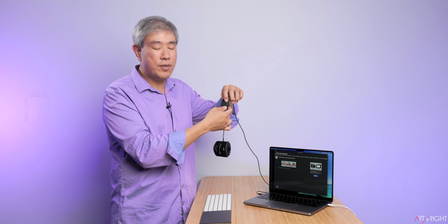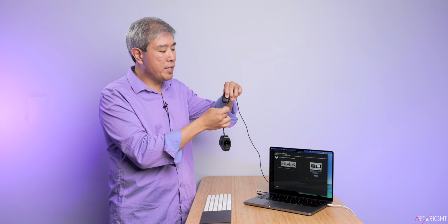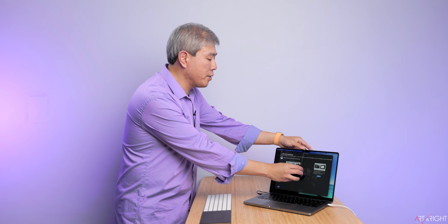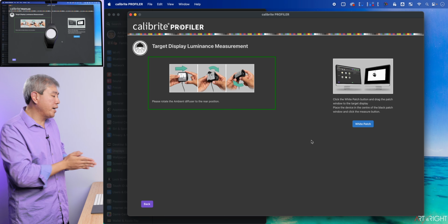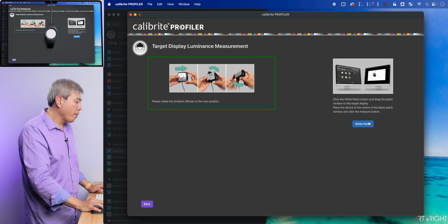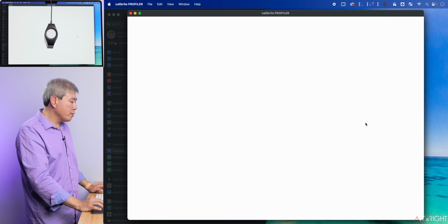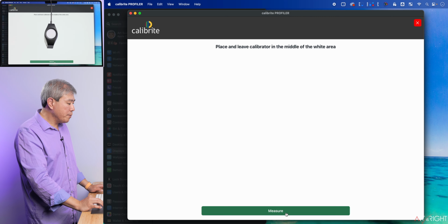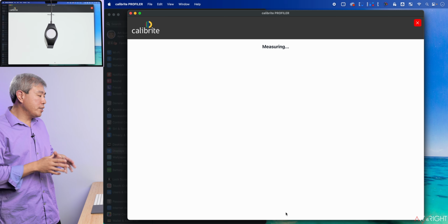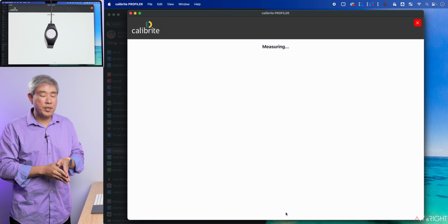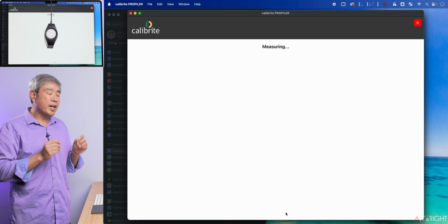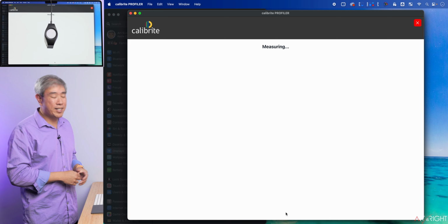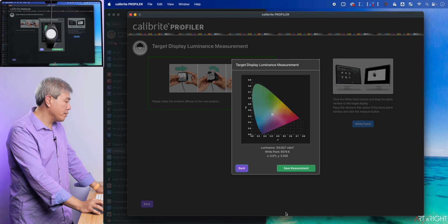I have this counterweight already adjusted. However, if you need to adjust it, you just simply press down, and it's going to be just a slight tug of the wire. It's not a hard pull or anything like that at all. I'm going to align this on the display like so, and I will tilt the display back this way to ensure that the device is laying flat on the display. I'll click on that blue button, white patch, and once that shows up, I'm simply going to click on measure. This is going to now measure the white point output of our display, including the XY coordinate as well. And these are the values that we're going to need to input into the dialog in system settings.